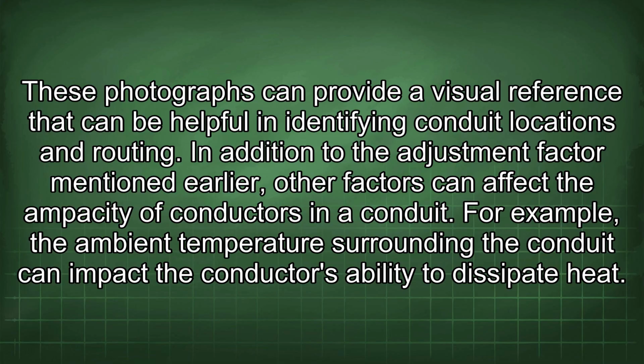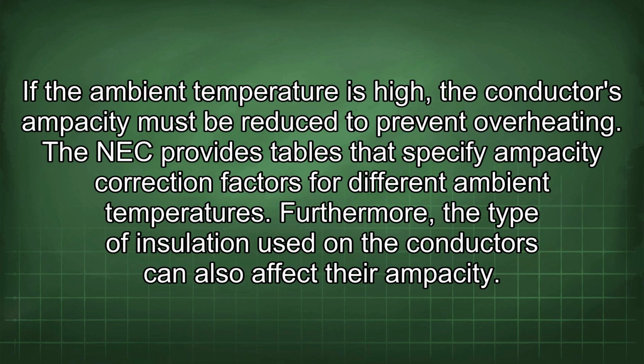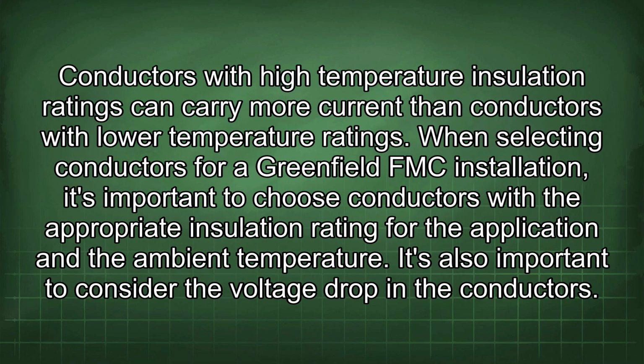In addition to the adjustment factor mentioned earlier, other factors can affect the ampacity of conductors in a conduit. For example, the ambient temperature surrounding the conduit can impact the conductor's ability to dissipate heat. If the ambient temperature is high, the conductor's ampacity must be reduced to prevent overheating. The NEC provides tables that specify ampacity correction factors for different ambient temperatures. Furthermore, the type of insulation used on the conductors can also affect their ampacity. Conductors with high temperature insulation ratings can carry more current than conductors with lower temperature ratings. When selecting conductors for a Greenfield FMC installation, it's important to choose conductors with the appropriate insulation rating for the application and the ambient temperature.